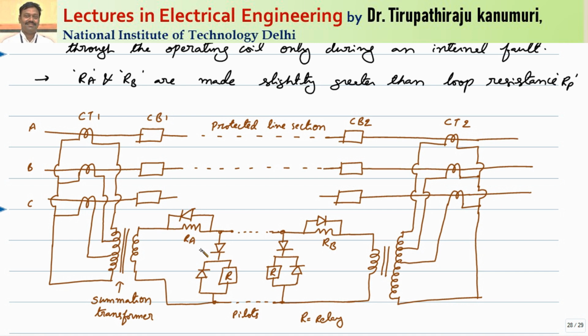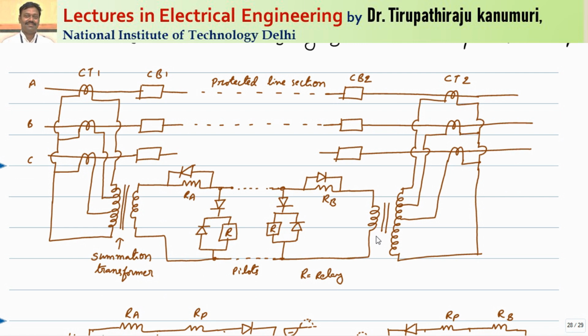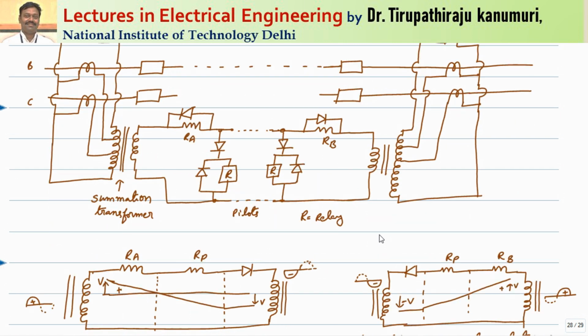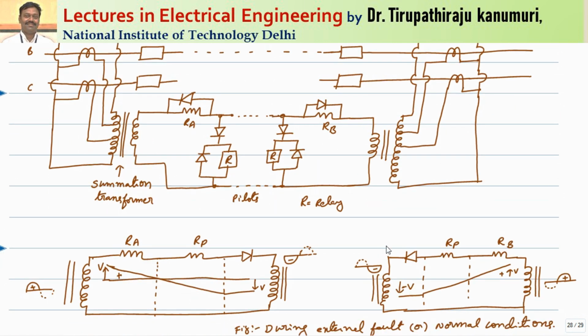So while designing, we will design in such a way that the values of RA and RB will be slightly greater than the loop resistance of your pilot wires. These are the pilot wires. These two relays will be at the sending and the receiving end respectively. Accordingly, they will trip their respective circuit breakers at those locations. So let us see how this will operate under normal operating conditions.